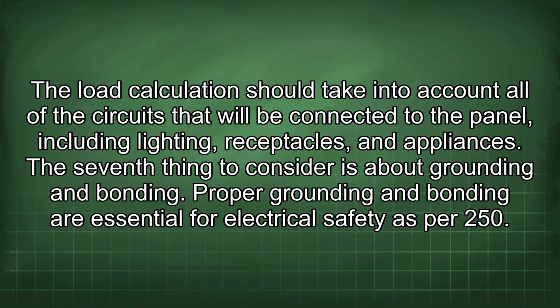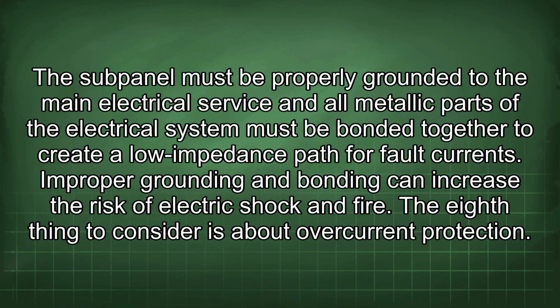Proper grounding and bonding are essential for electrical safety as per 250. The subpanel must be properly grounded to the main electrical service and all metallic parts of the electrical system must be bonded together to create a low impedance path for fault currents. Improper grounding and bonding can increase the risk of electric shock and fire.